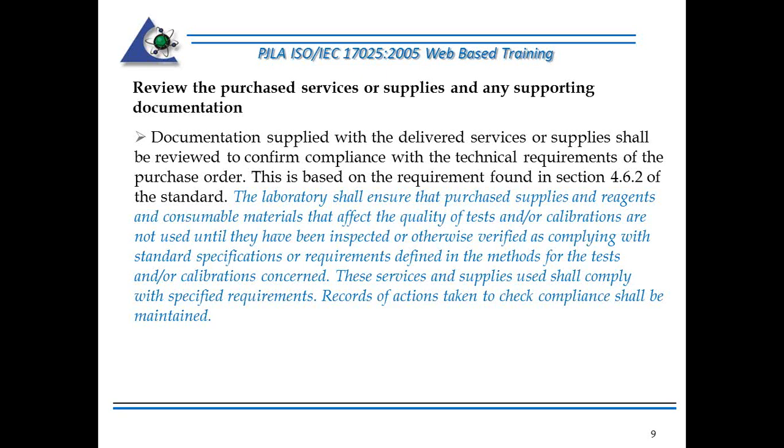It will reference standards that specify how that material is to be prepared, and the laboratory is responsible for making sure that the information reported to them satisfies the reporting requirements of the accreditation or the oversight body that is responsible for authorizing the production of certified reference materials. On the other hand, if it's a calibration, you don't get a packing slip on a calibration. You get a calibration certificate.